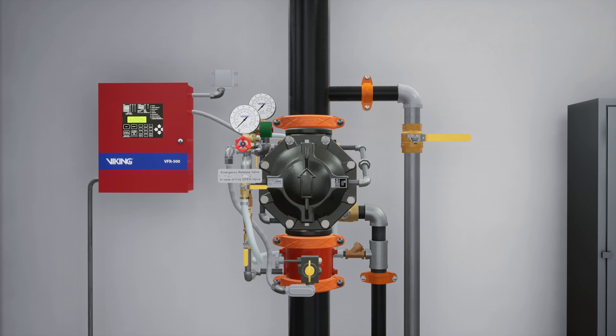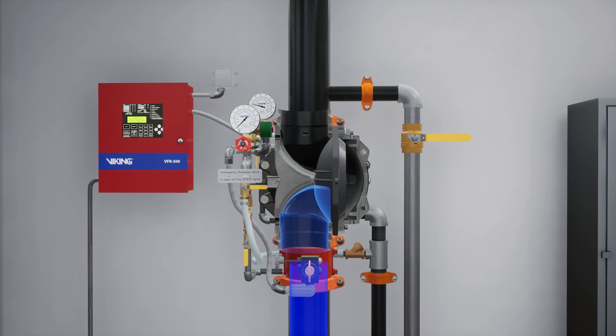The VXD Deluge valve is a flood valve with only one moving mechanism. The valve is held closed by priming water pressure trapped in the priming chamber. This keeps the outlet chamber and system piping empty.